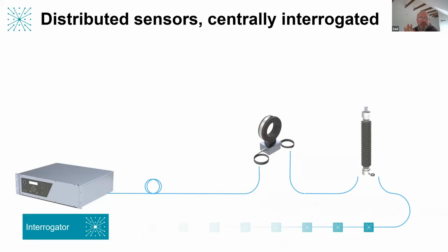So at a very simple level, to understand the concept behind this technology that Tom and Steve are going to take you through, the thing to learn here is that we install one smart device, normally in a substation, or it could be onshore or offshore substation in this case, which connects to a single fiber, and then we can reach out over very long distances and integrate into that fiber new or retrofitted sensors. Now, these are completely passive. The only thing connecting a sensor far away from that interrogator box is encoded light traveling forwards and backwards through that cable. There is no data, and the CTs and VTs you can see here are industry standard ones.